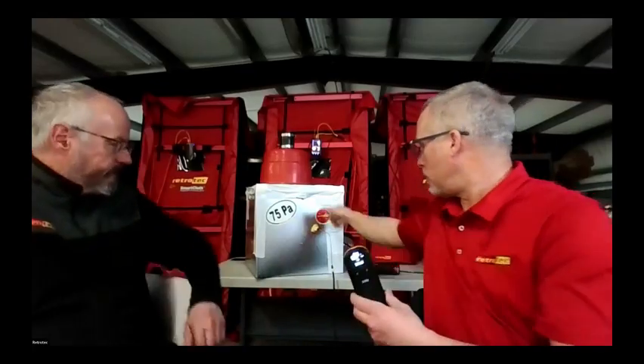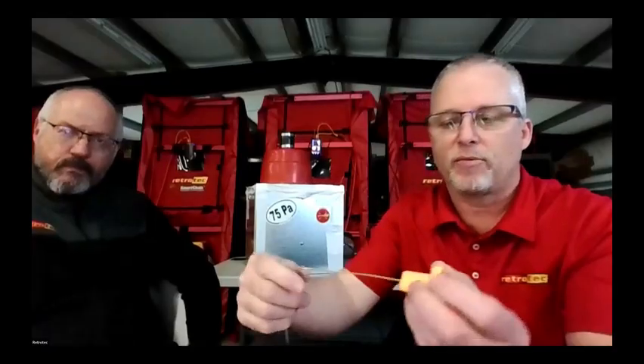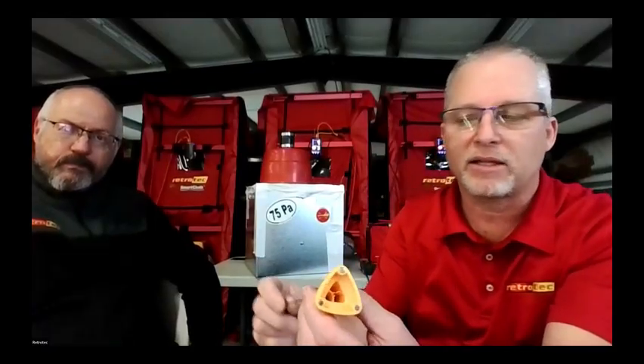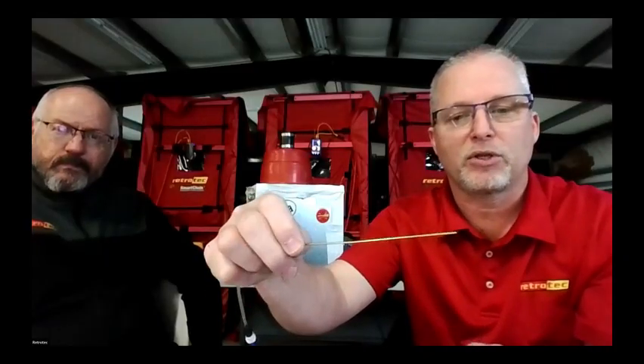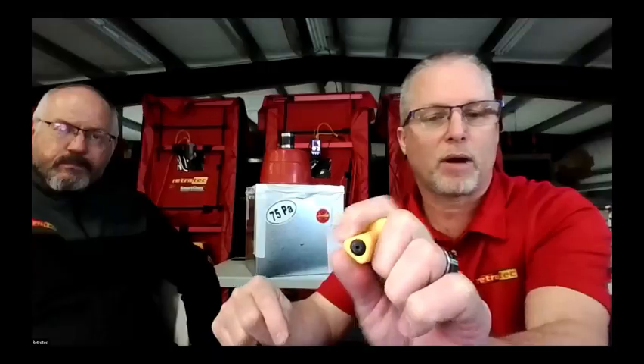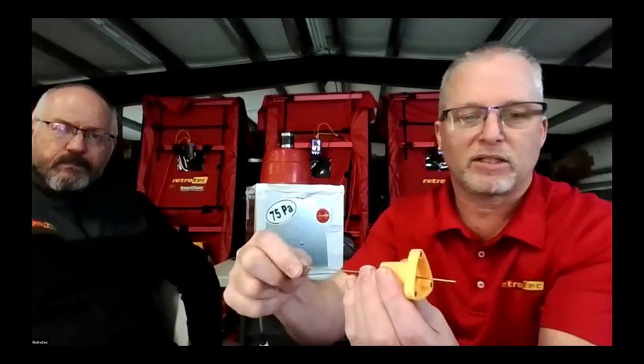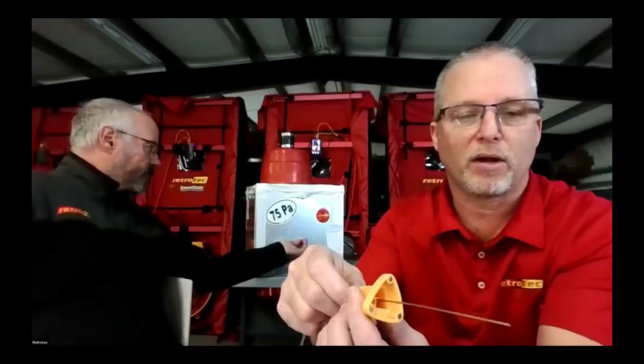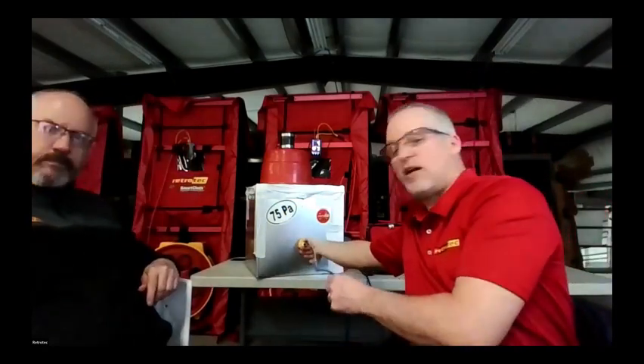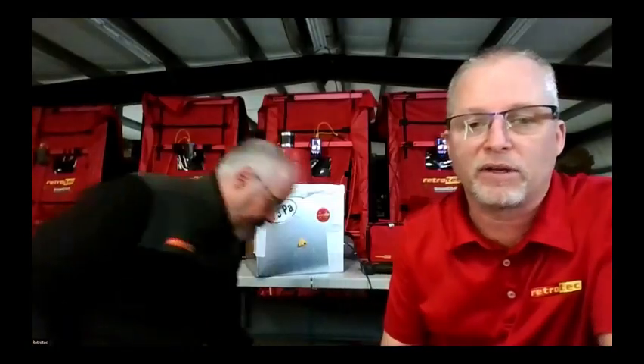You can use it with a mini probe, or actually this is the multi-probe unit. It's a little holder that's got 3 magnets on it. It's a small diameter tubing that slides through a rubber grommet. You can adjust the depth that way, or you can slide it all the way in and use it for other units, like sliding under. If you remove a screw and put it on the side of an air handler, it'll hold itself in there. Or on an ERV or HRV, you can remove the ports the manufacturer may have provided and slide it in there, and it'll hold on. So if one is mounted horizontally, it will hold itself to it instead of having to rely on the tube to come out.